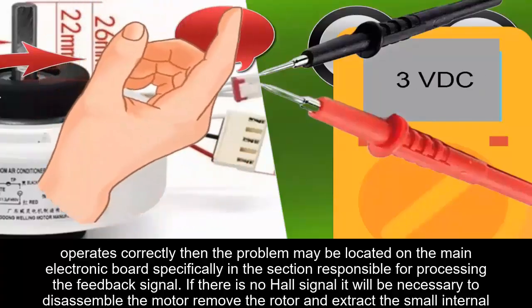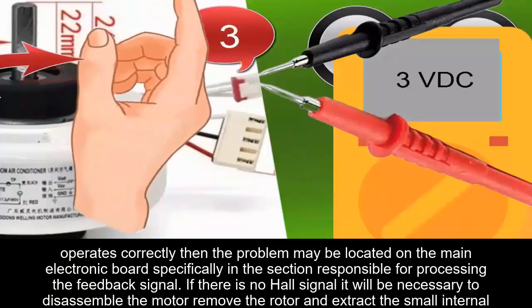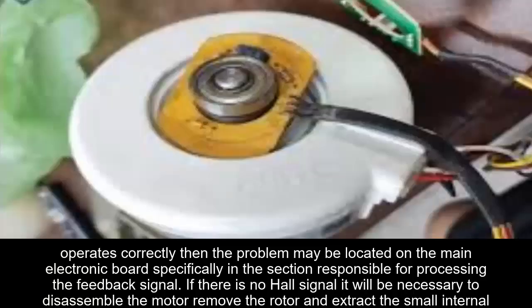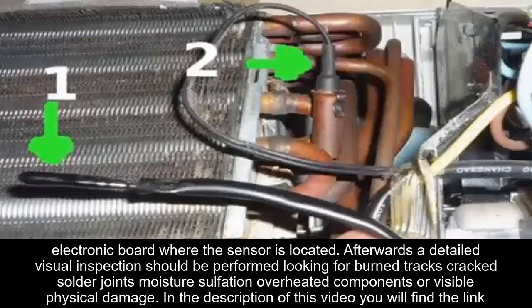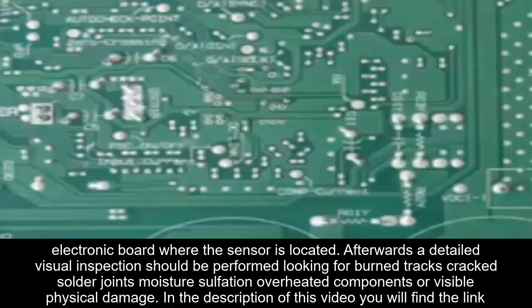If there is no Hall signal, it will be necessary to disassemble the motor, remove the rotor, and extract the small internal electronic board where the sensor is located.